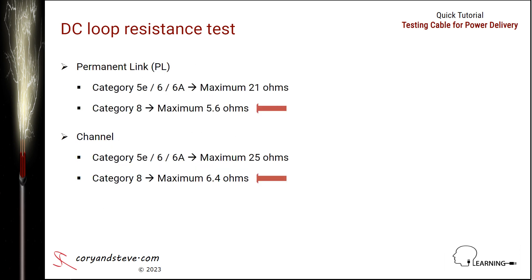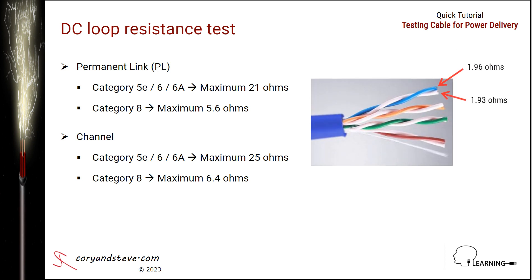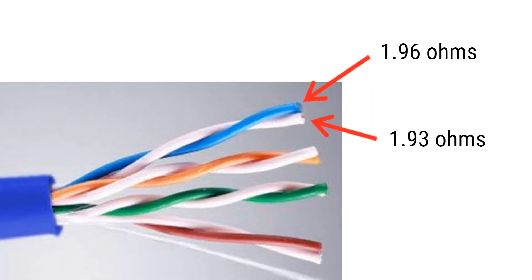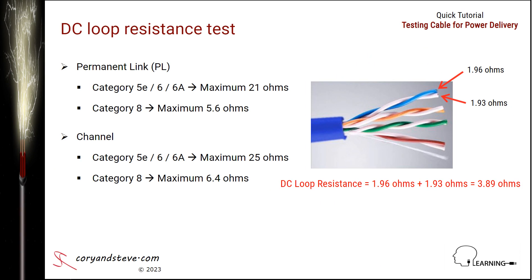The maximum allowable DC loop resistance values for permanent links and channels are listed here. Note that the category 8 limits are lower than the limits for categories 5E, 6, and 6A because of the shorter permanent link and channel length limits for category 8. In the example shown, the DC loop resistance for pair 1, the blue pair, is measured to be 3.89 ohms, well below the 21 ohm limit for a permanent link and 25 ohm limit for a channel, so this pair passes the test.